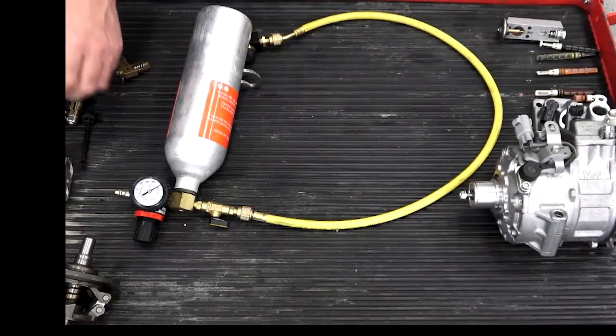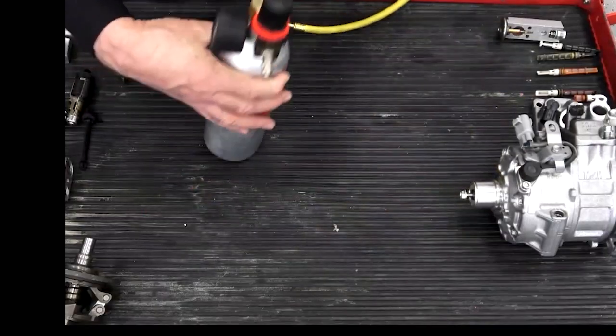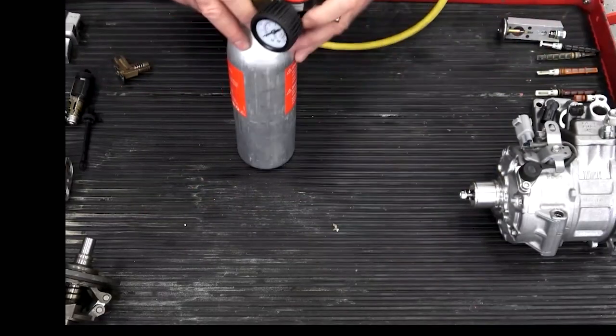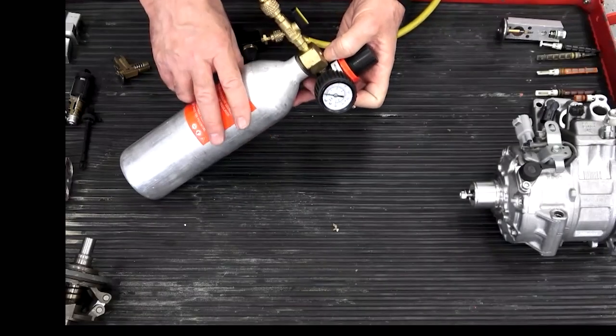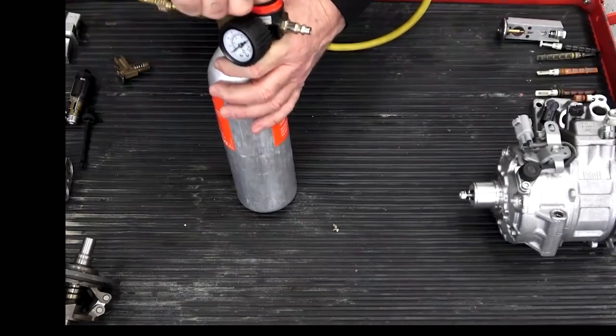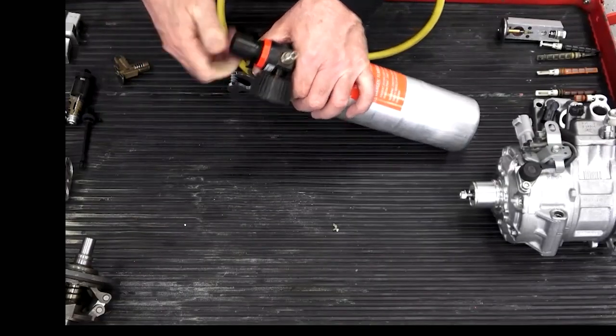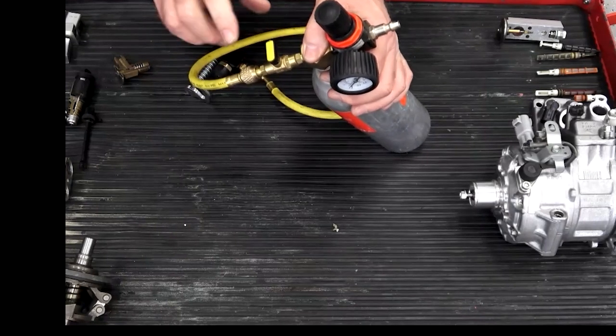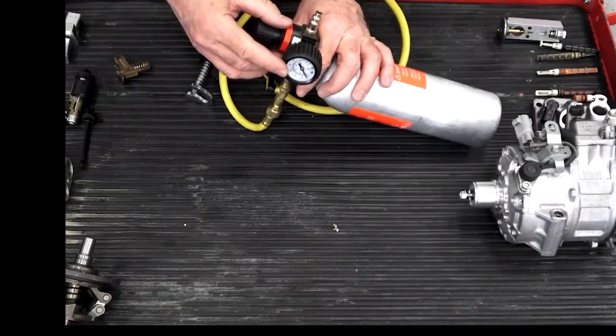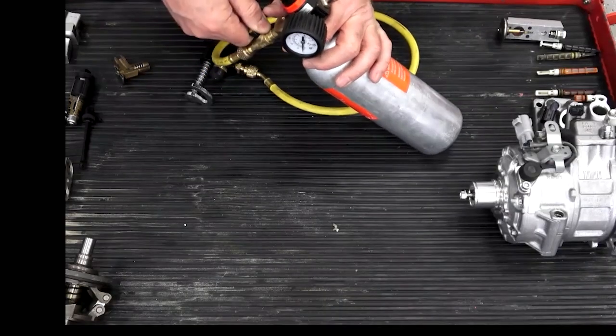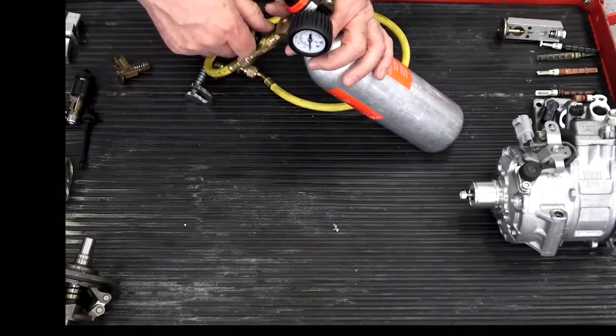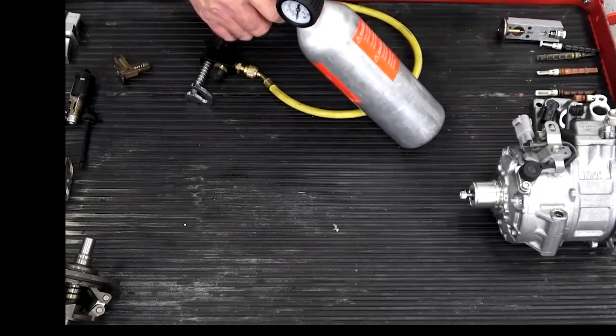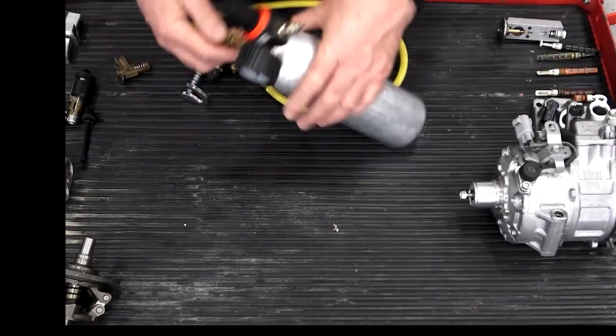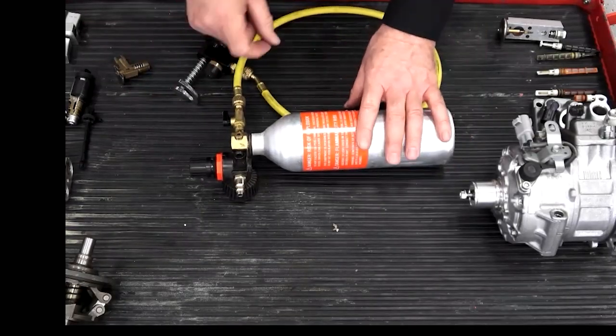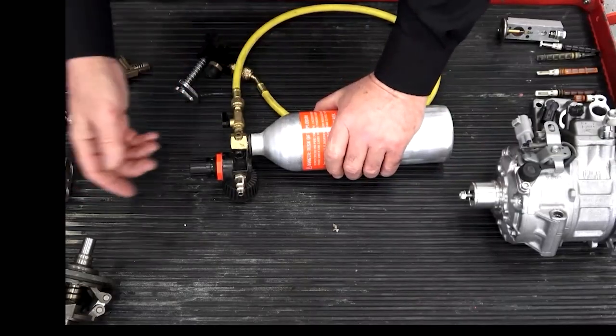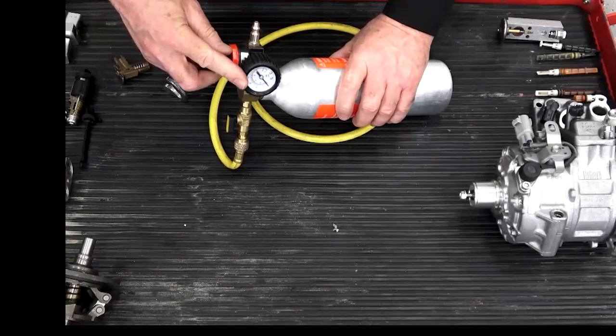A much better tool is what we're looking at here. It's got an air chuck, so I can connect up shop air to it. It's got a pressure gauge, so I can actually control the pressure through the evaporator. It's also got a shut-off valve, so I can dial the pressure up to, let's say, 40 psi, and then give it a squirt very quickly to soak the evaporator for a little bit. Then I turn the shut-off valve back on, and the continuing air pressure maintains the solvent momentum through the evaporator to prevent any kind of solvent dropout. And when all the liquid is expelled, which only takes a few seconds, I dial the pressure up to 80 psi, and I walk away.